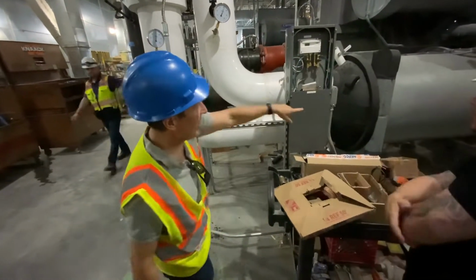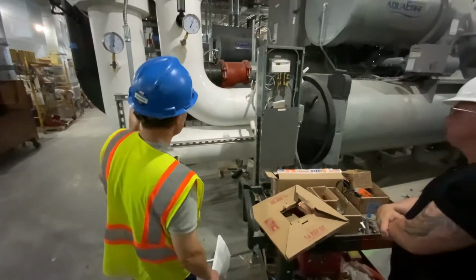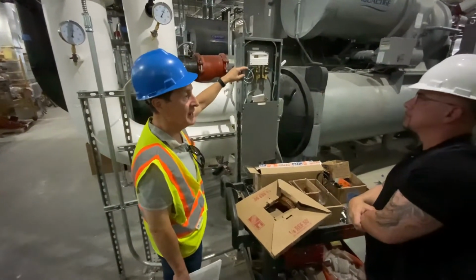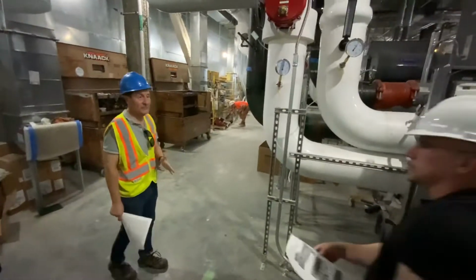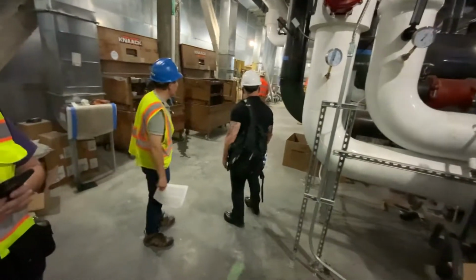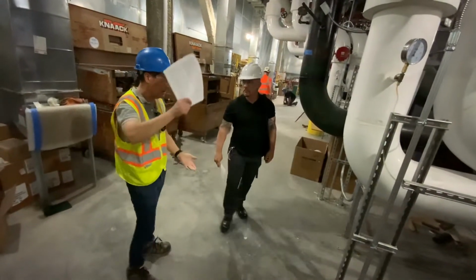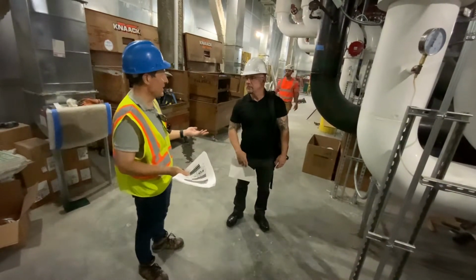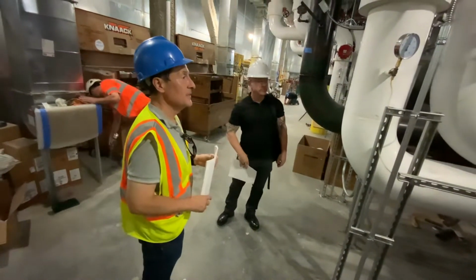Yep. So the chiller is obviously the cooler side here because it's insulated, so it's lower than the condenser. They're going to vary the flow through the chiller until it reaches a minimum set point value that the BMS system has in here. And when that is hit, to not go below it, because that could be bad for a chiller, there's a bypass valve down at the end of the loop over there, and that valve starts to open to maintain the minimum flow rate. So the chiller can vary the flow between a low and a high. I don't have it with me, but it's in the submittal data if you want to know what it is. And so this is the cooler.